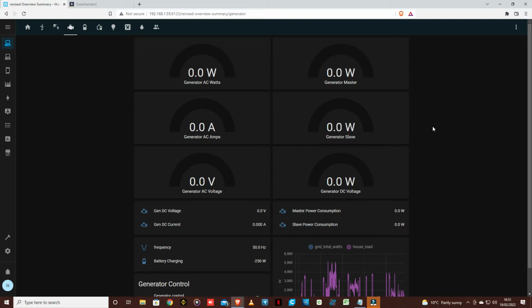So I wanted to also know, however, what is the DC side of our generator. We're not operating on a brushless system. It is brushed, it is basic, and it's straightforward what you can purchase pretty much off the shelf. So nothing really special, and to all degrees the cheaper generators are going to be no more generic than what we have. So I want to know what the DC side is doing. I also want to know DC voltage for the brushes, DC current, DC amperage, all those kind of things.